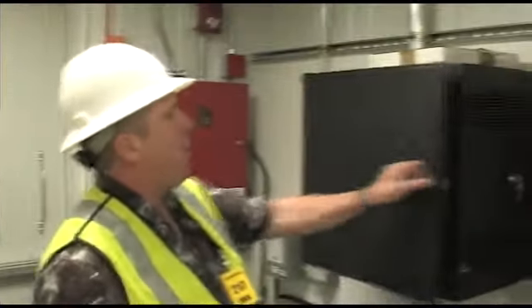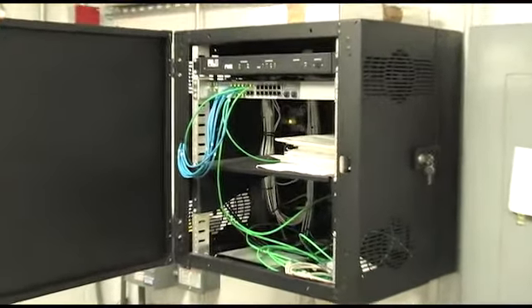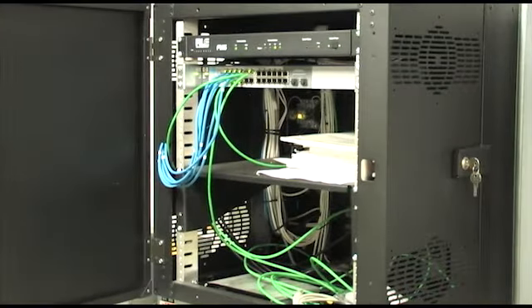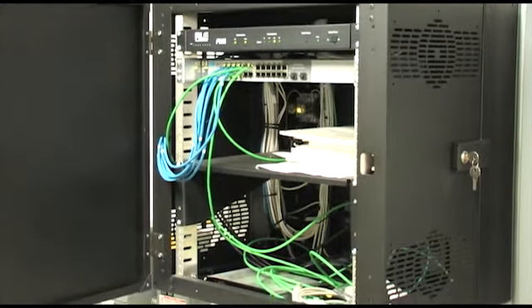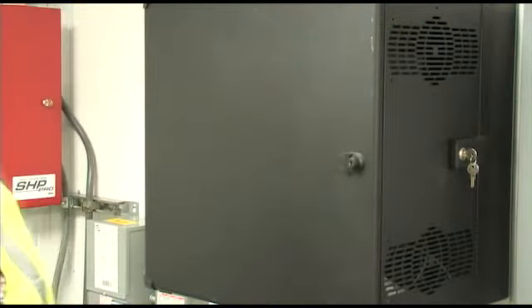This is where the Falcon, which is a communication module that communicates with the building as well as with other components inside the module. This module has a 500 kW UPS system, Mitsubishi 9900 B series. This system is dual fed with two sources, one from the maintenance bypass and one directly to the unit.